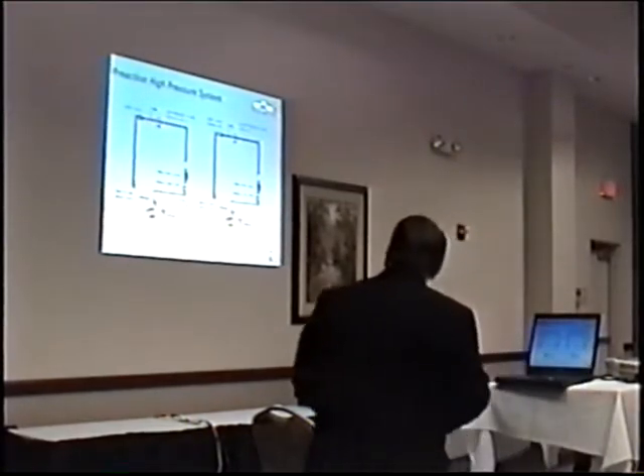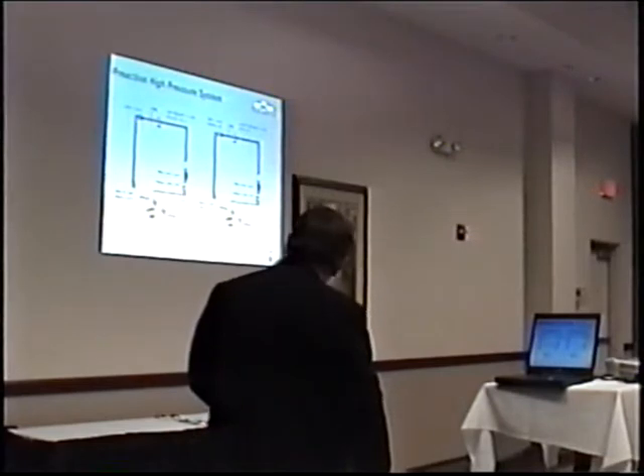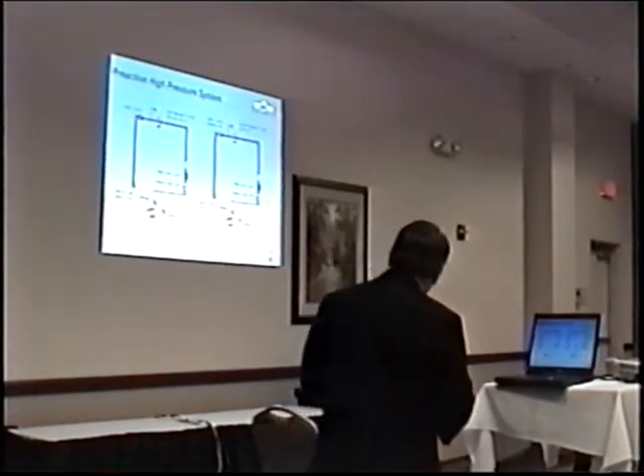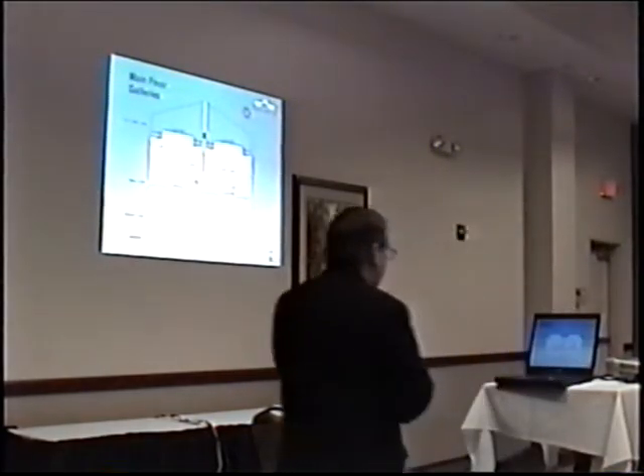So the 110 bar, I'm not going to go into the accumulator system I put on to prevent direct filling with the pump, but this is full of air. When the system operates, the deluge valve opens. This is now full of water. The air is trapped on that side of the check valve and can't act on the nozzle portion of that system. So then phase 2 comes along.